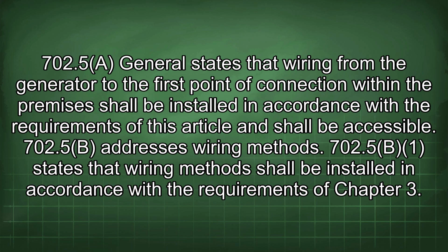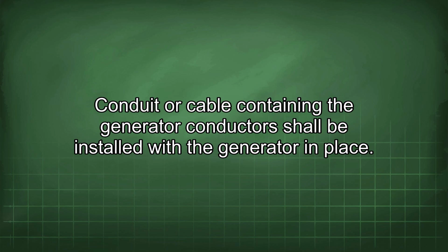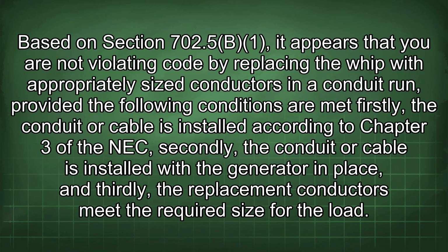702.5(B) addresses wiring methods. 702.5(B)(1) states that wiring methods shall be installed in accordance with the requirements of Chapter 3. Conduit or cable containing the generator conductors shall be installed with the generator in place. Based on Section 702.5(B)(1), it appears that you are not violating code by replacing the whip with appropriately sized conductors in a conduit run, provided the following conditions are met.